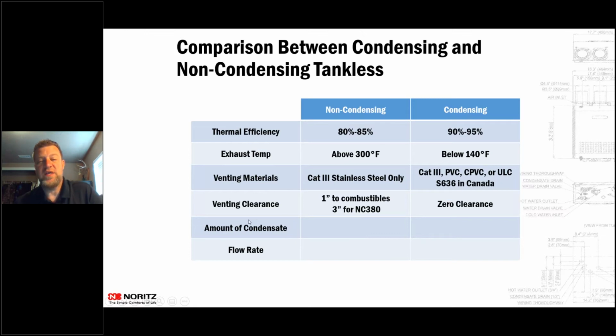So venting clearances with old non-condensing, that stainless steel, you had to have like 1-inch clearance to combustibles, or some manufacturers required like 2 inches to the side, 4 inches below, and 12 inches above, and all these different things. But with condensing units, you can run it in PVC and plastic materials where it's 0 clearance to combustibles, so you can run it through a joist space, through insulation, through the girder at the side of the house, with 0 clearances to any of those going out.